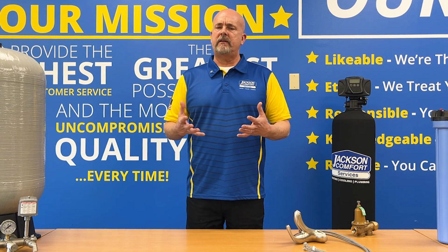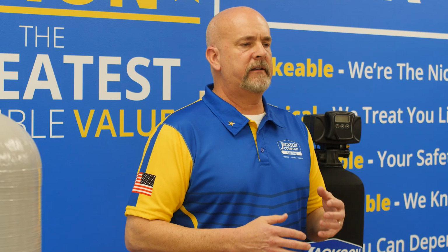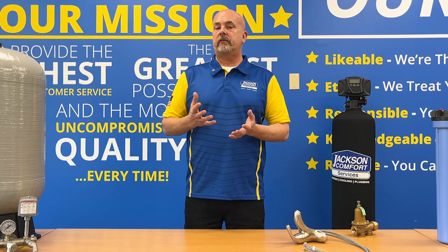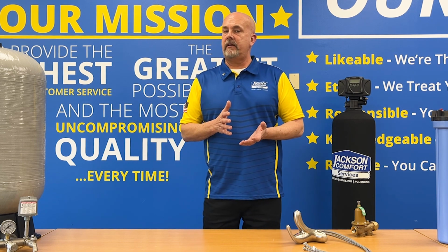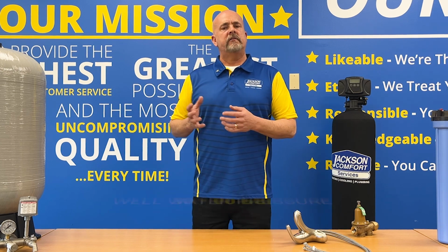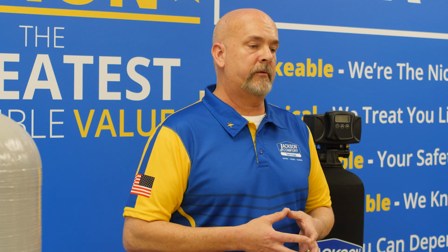One of the main differences is city water pressure, even if we're regulating it, is around 75 psi. For those of you who are new to a well or have never been on a well, water pressure generally fluctuates, and it can fluctuate anywhere from, at the bottom end, 30 to 40 psi up to 60 psi. So even generally at its high end, it doesn't reach the same pressure that city water reaches.